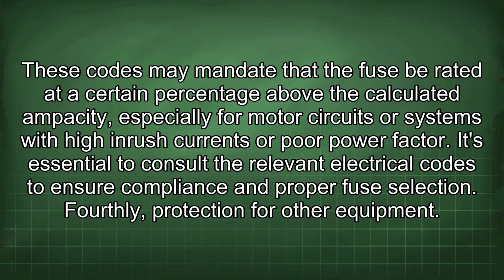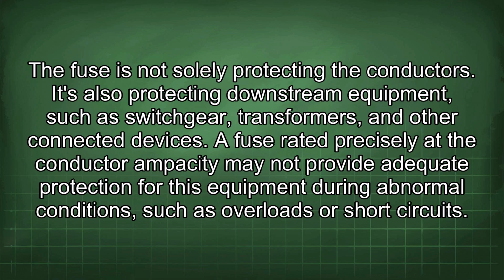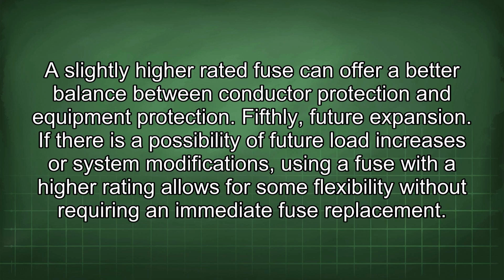Fourthly, protection for other equipment. The fuse is not solely protecting the conductors. It's also protecting downstream equipment, such as switchgear, transformers, and other connected devices. A fuse rated precisely at the conductor ampacity may not provide adequate protection for this equipment during abnormal conditions, such as overloads or short circuits. A slightly higher rated fuse can offer a better balance between conductor protection and equipment protection.